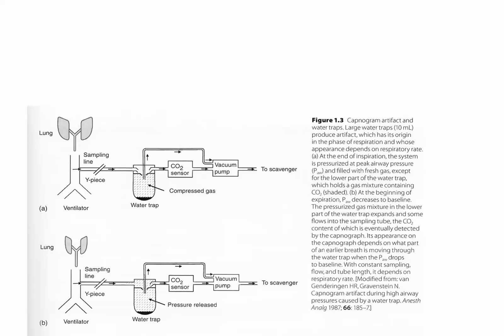Sidestream capnometers have problems associated with them, one of the more interesting being related to the water trap. During inspiration, the system is pressurized, creating an area above the compressed gas that is devoid of CO2, while compressed gas below contains CO2, indicated by the gray shading in the figure. When pressure is released, that compressed gas comes back up and enters the sampling tubing, potentially producing an artifact in the value reported by the capnometer.